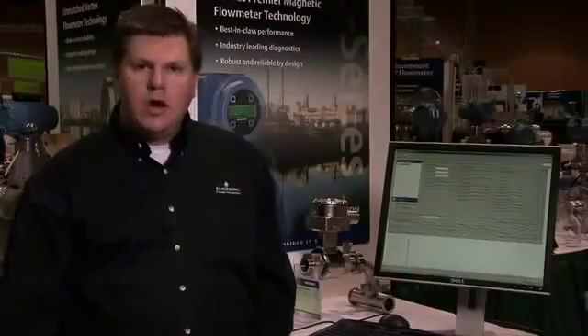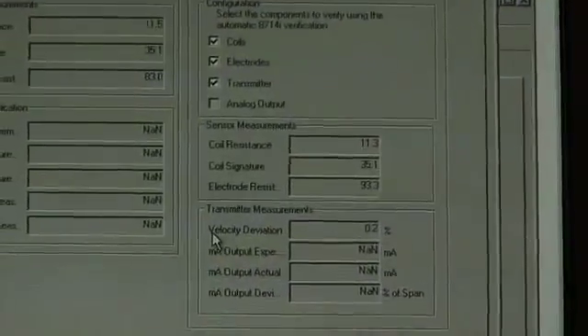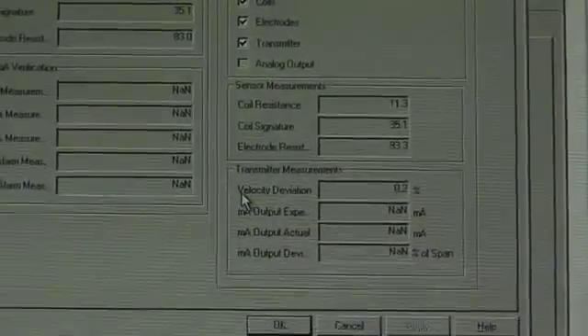With continuous meter verification, you again have the ability to tell the system what it is that you want to continually check. And this is operating in the background of the device without affecting the flow measurement or the primary output coming out of the transmitter. Those values and that configuration is also available to view.